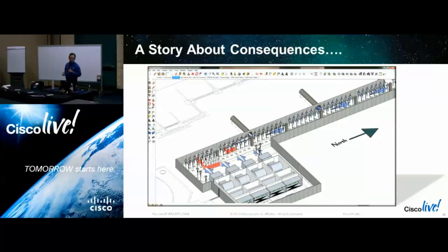So Chris and I went in, and what we're looking at here is part of a 3D model that we build as a part of these assessments so that we can communicate the root causes and some of the complexity visually. What we're looking at here is just the air tunnel that was underneath the data hall. This was an early free air design. It was architected by building architects, and they didn't have a lot of experience in what data centers needed, and the filtration reflected that. So they had inadequate filtration.